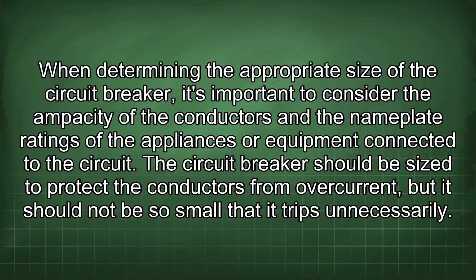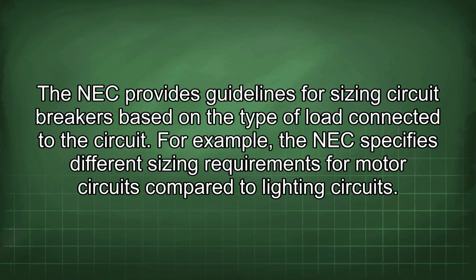When determining the appropriate size of the circuit breaker, it's important to consider the ampacity of the conductors and the nameplate ratings of the appliances or equipment connected to the circuit. The circuit breaker should be sized to protect the conductors from overcurrent, but it should not be so small that it trips unnecessarily. The NEC provides guidelines for sizing circuit breakers based on the type of load connected to the circuit. For example, the NEC specifies different sizing requirements for motor circuits compared to lighting circuits.